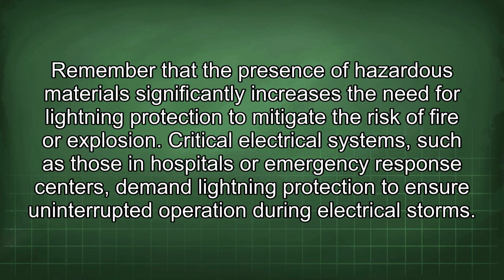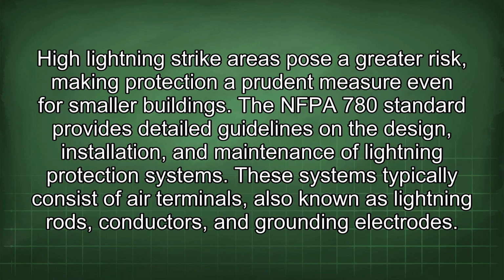Remember that the presence of hazardous materials significantly increases the need for lightning protection to mitigate the risk of fire or explosion. Critical electrical systems, such as those in hospitals or emergency response centers, demand lightning protection to ensure uninterrupted operation during electrical storms. High lightning strike areas pose a greater risk, making protection a prudent measure even for smaller buildings. The NFPA 780 standard provides detailed guidelines on the design, installation, and maintenance of lightning protection systems.